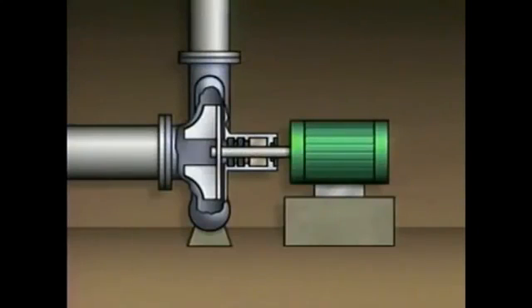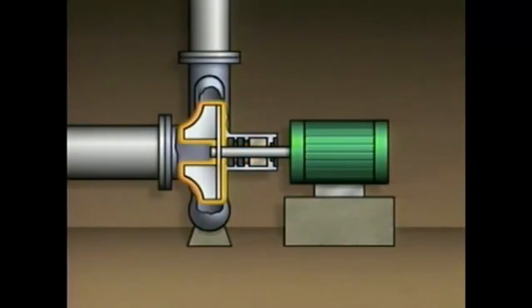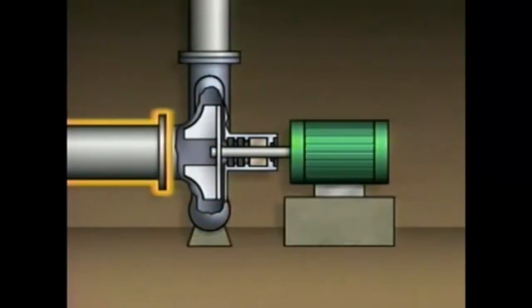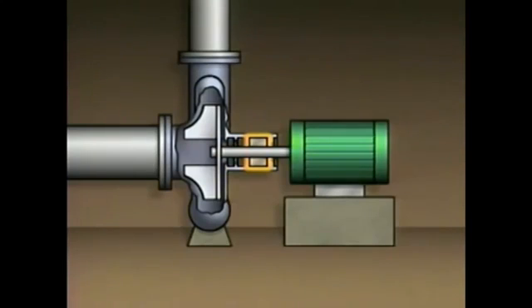Let's look at single-stage compressors first. This simplified illustration is a side view of a single-stage centrifugal compressor. The compressor's main components include a shaft, which is connected to a motor, seals, a shaft bearing, an impeller, the compressor casing, which contains a volute, a suction line, and a discharge line. The shaft is used to rotate the impeller, powered by an electric motor. The seals prevent gas from leaking out of the compressor and lubricant from leaking out of the bearing along the shaft. The shaft bearing supports the shaft and allows the shaft to rotate.